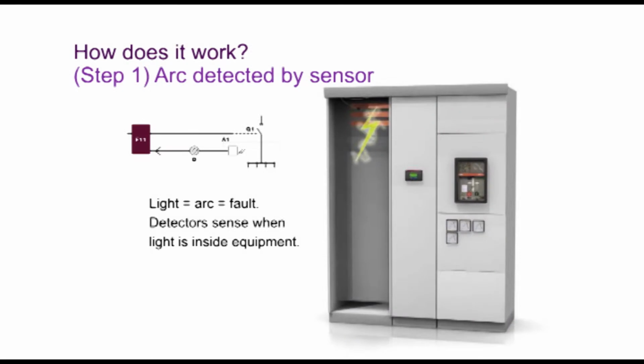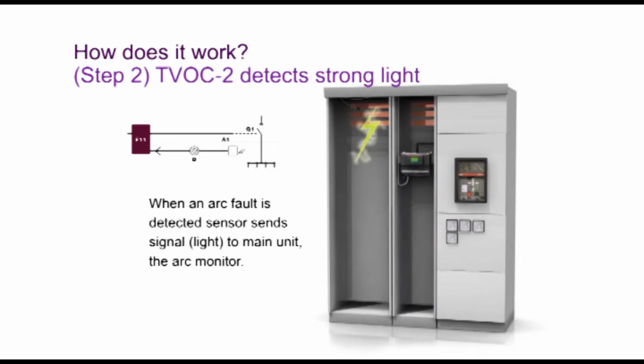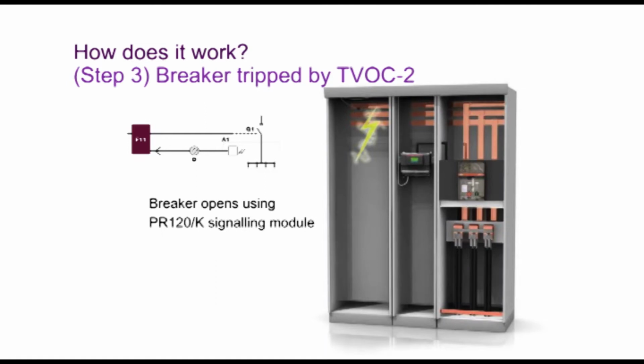How it works, it's a very simple system. The light sensors and the fiber optic cables detect if an arc occurs, and send a signal to the TVOC unit. The TVOC unit then sends a signal to the breaker to trip the breaker. It's that simple.